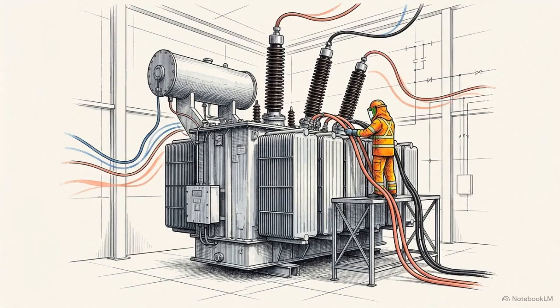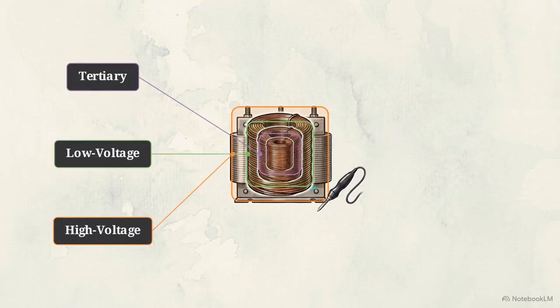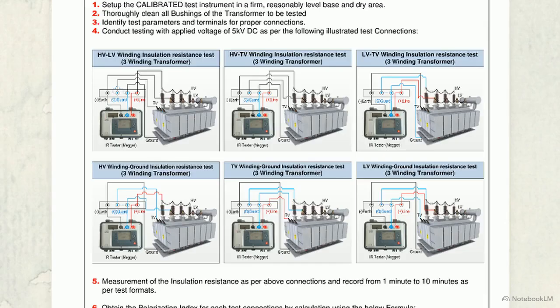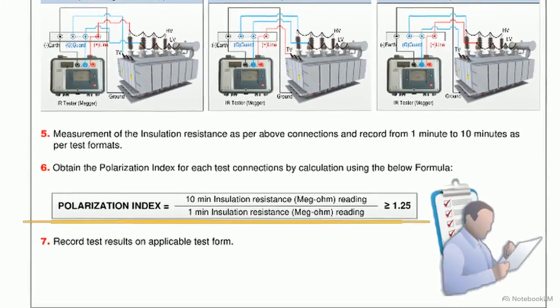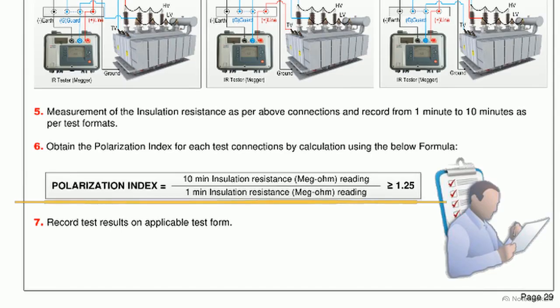The active sequence begins by verifying the dielectric health of the asset, starting with winding insulation resistance, or IR testing. We apply 5 kilovolts DC to the high voltage, low voltage, and tertiary windings. This document shows 6 connection diagrams isolating specific boundaries. We analyze this data by calculating the polarization index, the ratio of the 10-minute to the 1-minute resistance reading. A PI of 1.25 or greater proves the insulation aligns dipoles properly under sustained stress.